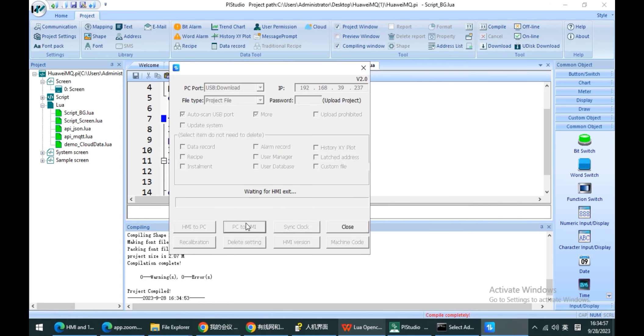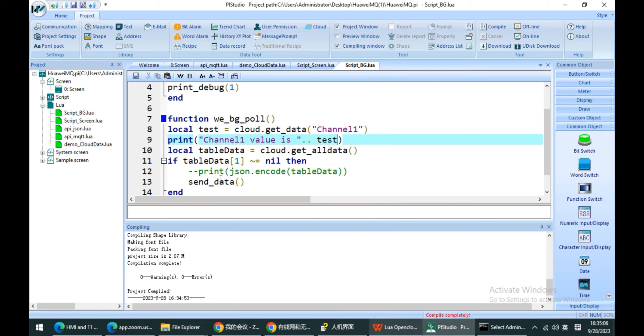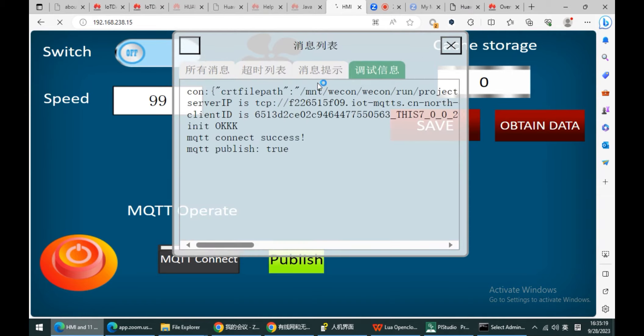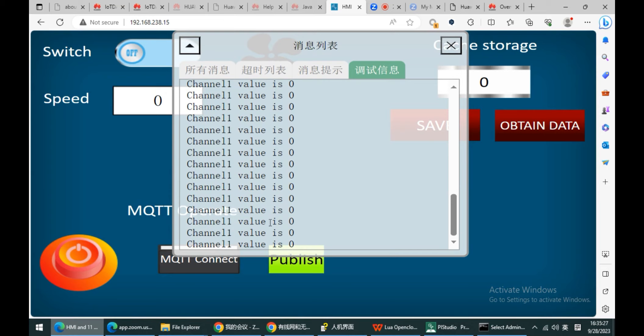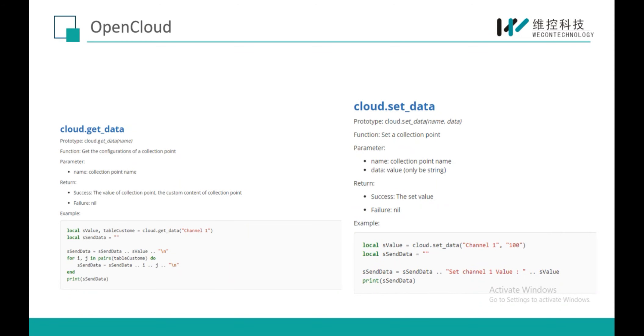I download into my HMI. Wait for the HMI to come online. We can see it prints the channel one value. It is still showing initial values because I didn't initiate the HDW50 register. That is how get-data works — we can directly use the name to get the data. Set-data works the same way.